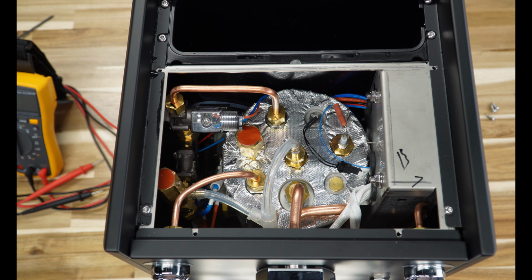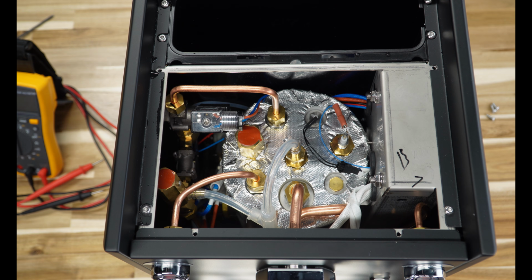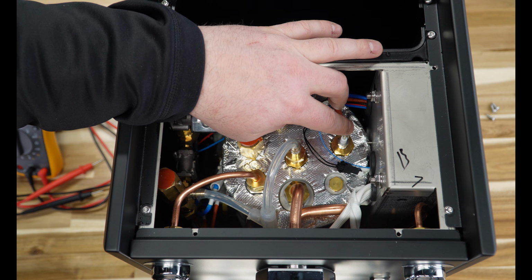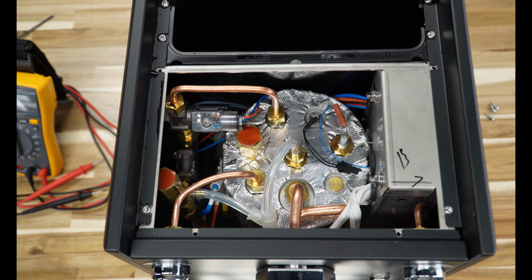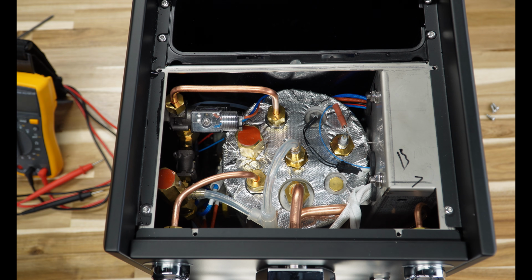So why is this a big deal? Well, sometimes these do get corrosion on them, and you need to pull them out and clean them. The other reason that we see is you're using too pure water, so we say don't use RO water. The reason for that is RO water doesn't conduct electricity. So if this is not able to conduct electricity through it, it's not going to know that the boiler is full - it's actually going to just continue to run and run and run until it's over full.